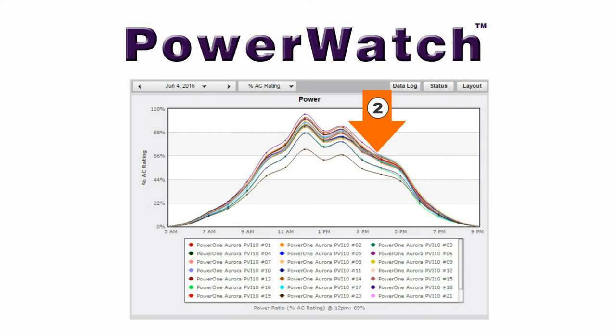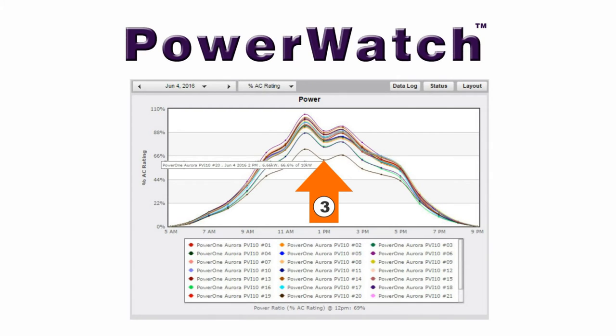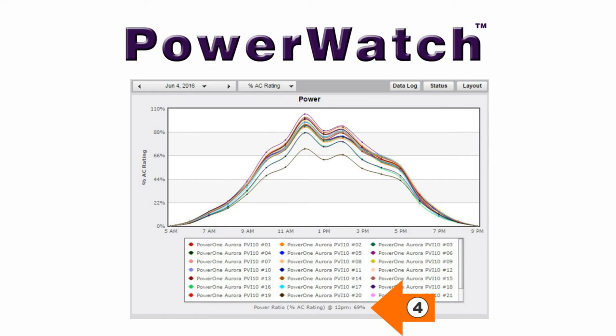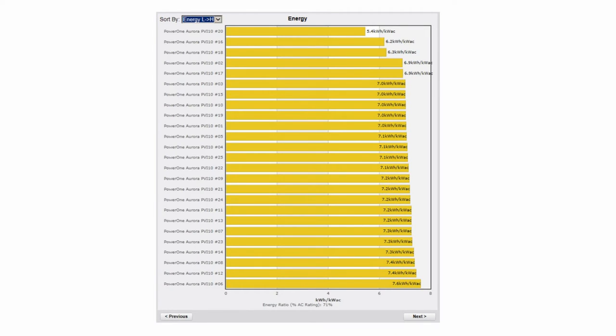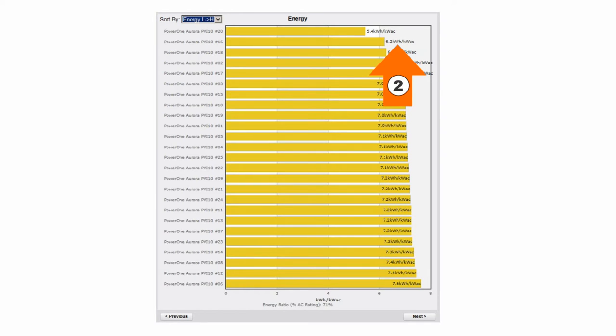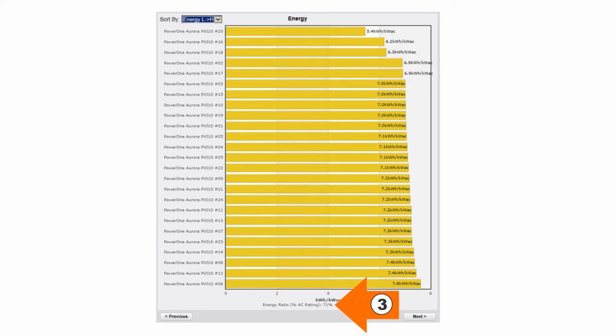Scroll your mouse over the lowest inverter to get a pop-up of the inverter name and its current output. The power ratio shows the maximum difference at 12 noon — 100% is a perfect match, and a value lower, like that shown here, indicates a potential problem. Below the power output graph is the energy bar chart that shows the daily generation from each inverter. Use the sort-by pulldown to display from lowest to highest to quickly identify a suspect inverter. The output can be shown as daily kilowatt hours, or if different size inverters are used together, select percentage of AC rating to normalize the display for output per kilowatt AC capacity so they can be compared. The energy ratio at the bottom of the bar chart shows the variation between the highest and lowest daily inverter energy output — 100% is a perfect match, and low values indicate a possible problem.